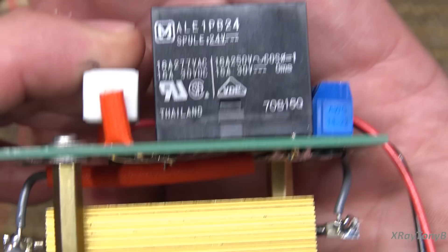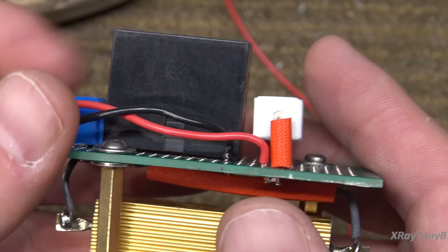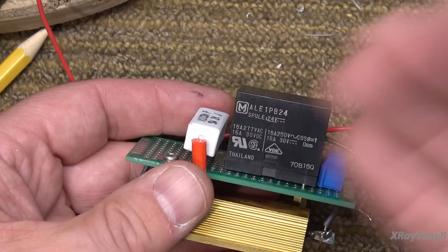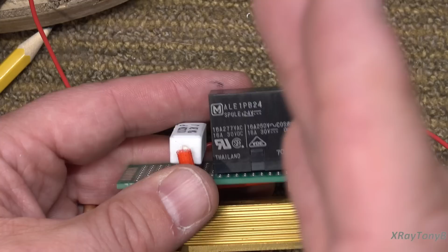So here it is. I'll show you both sides. And flip it, and there's nothing on that side. So this is the relay itself, and you can see it's got 16 amp contacts. And what we need to know is, first of all, this is a 24 volt coil. So the coil needs 24 volts nominally, but you're going to find out that a relay has a pull-in voltage, an operating voltage, and a do not exceed voltage. So on this one, the pull-in voltage is somewhere around 15 to 18 volts. It should run continuously at nominally 24 volts so that it holds the contacts in tight, but it can actually operate up to about 28 volts without really hurting it very much.